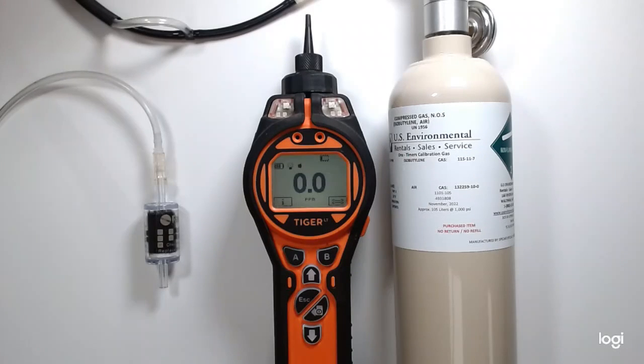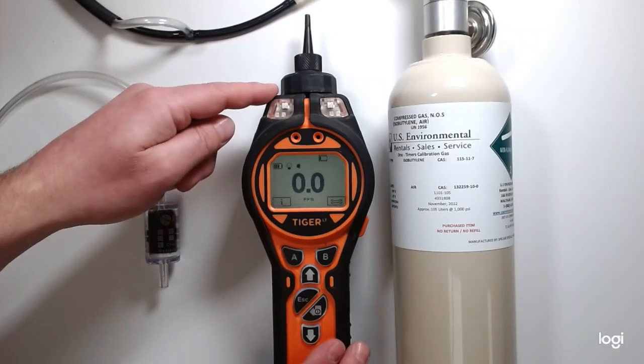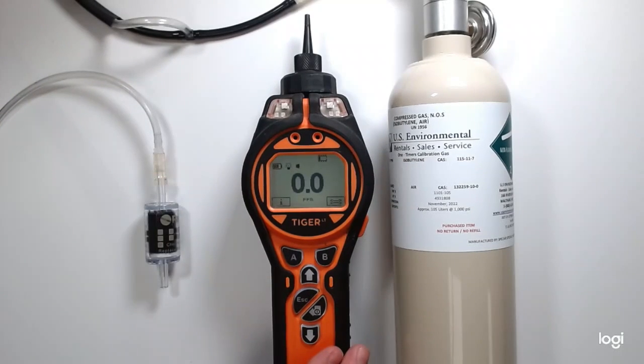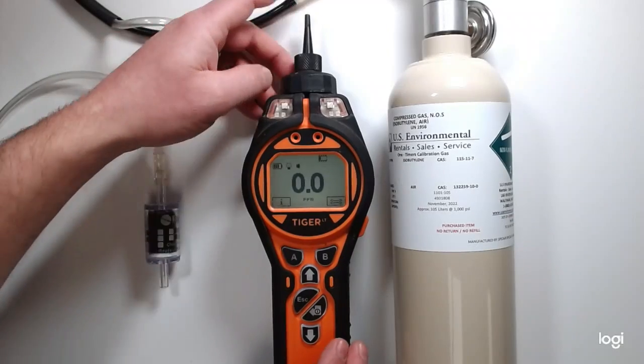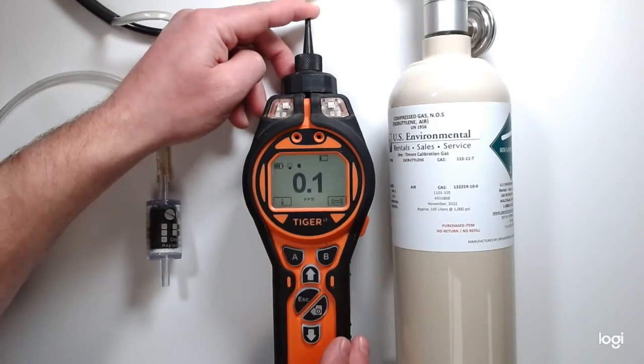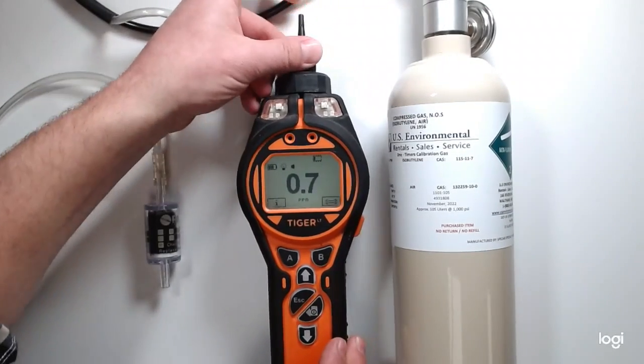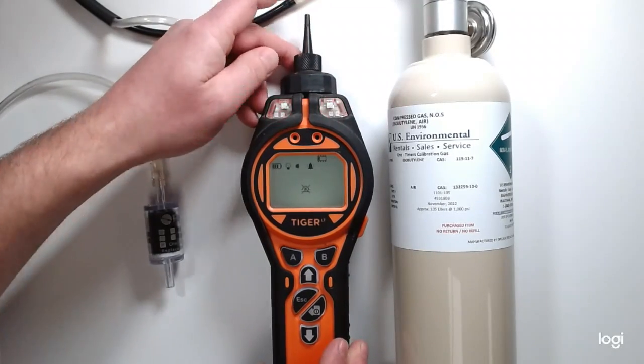This video is U.S. Environmental's basic calibration of an Ion Science Tiger PID. The first step would be to change the filter, which is under the probe tip. Once the filter has been changed, you should then proceed to check the pump. You should be able to stall the pump by putting your finger over the inlet.